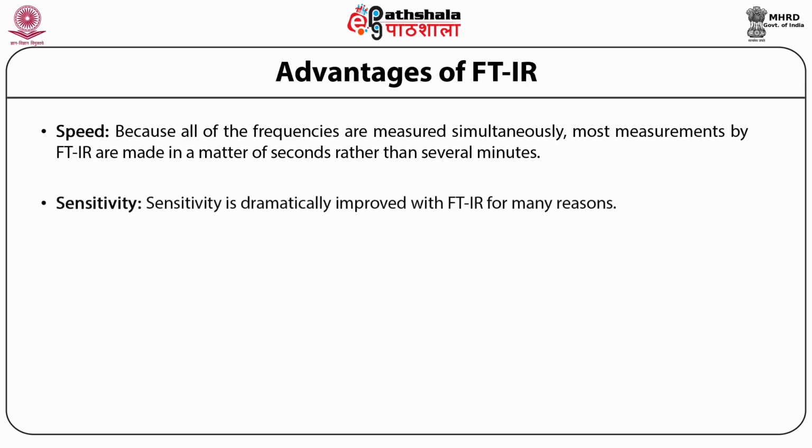Sensitivity: sensitivity is dramatically improved with FTIR for many reasons. The detectors employed are much more sensitive. The optical throughput is much higher, which results in a much lower noise level, and the fast scan enables the co-addition of several scans in order to reduce the random measurement noise to any desired level, referred to as signal averaging.